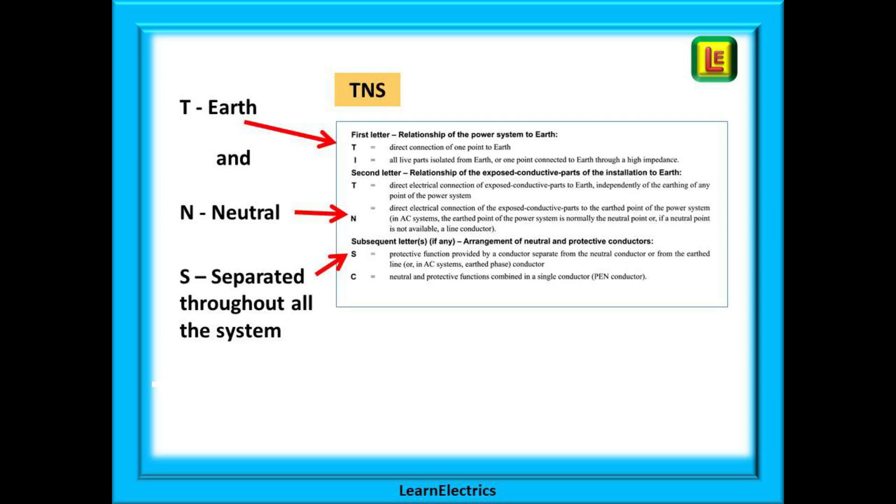Looking at TNS systems first. Take the T from the top section. It tells us this is a connection to earth. N from the second section is referring to the neutral. And finally S from the bottom part tells us that they are separate. So we have earth and neutral separate throughout the system. TNS.